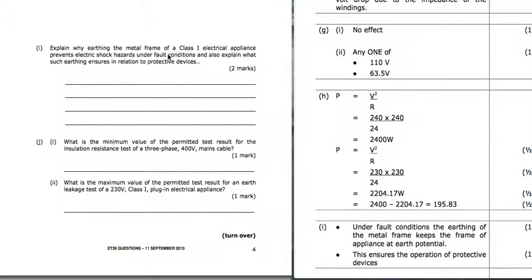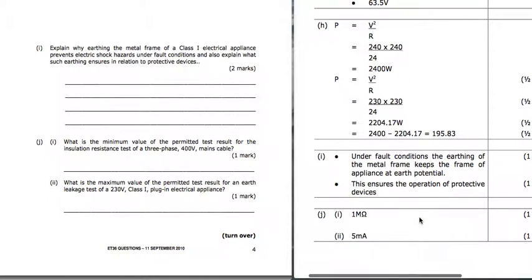Explain why earthing the metal frame of a class 1 electrical appliance prevents electric shock under fault conditions, and what it ensures in relation to the protective device. So under fault conditions, it will keep that frame at earth potential, at 0 volt potential. And in relation to the protective device, it will make sure it operates basically. It will give us a low resistance to give us lots of current to make that device operate.